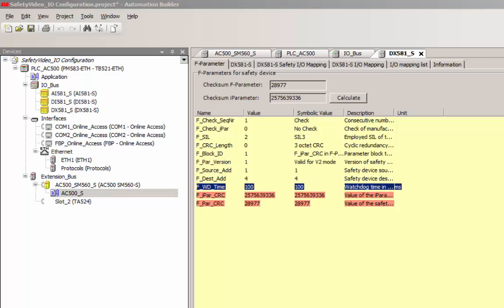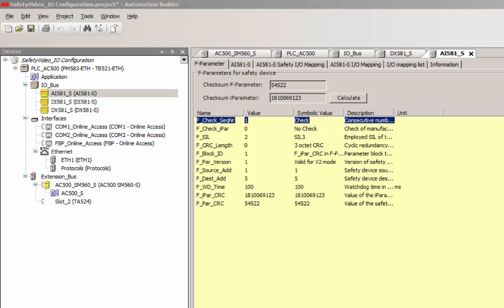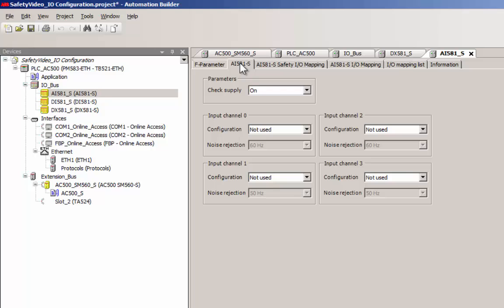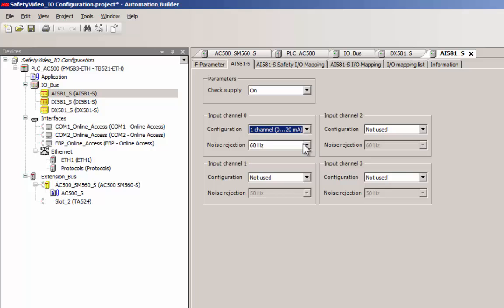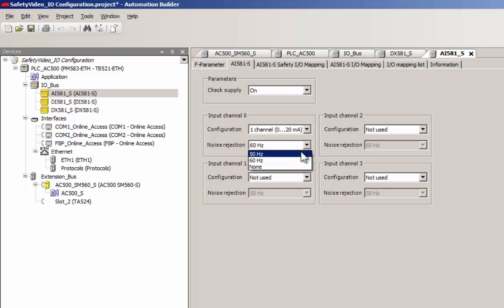Now we shall have a look at the configuration setting pertaining to a safety analog input module. An analog input channel could be configured as one channel for a signal range of either 0 to 20 or 4 to 20 milliampere.